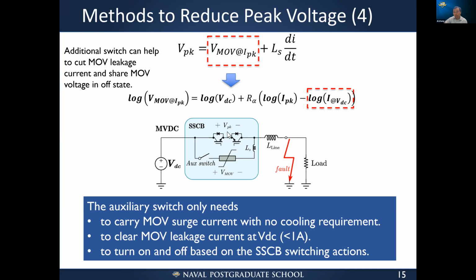For example, once I turn off the IGBTs, I want the devices to be turned on so the current can be commutated to the MOV, right? And once the MOV has decreased the current and cleared the fault current, when it carries a current below 1 amp, I want the device to be able to cut the current at that moment, right? And this cannot be done passively. If it's done actively, it's too complicated, and I'll end up bringing in a reliability concern for the component. Okay, so those are the key challenges.